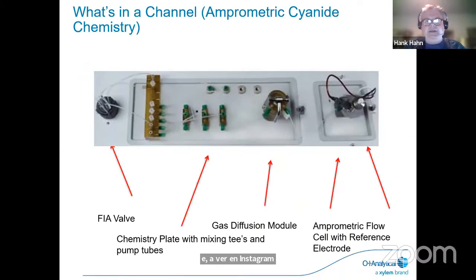So here's a breakout of what's in an amperometric cyanide chemistry. Those are done strictly with flow injection. And again, as I mentioned, with amperometric detection. Your chemistry plate with the required mixing tees and pump tubes for the reaction. We use the gas diffusion module. Again, we're eliminating the distillation step. With our total cyanide, we use the UV digestion lamp to help break down those bonds. And then you've got the amperometric flow cell with the reference electrode.